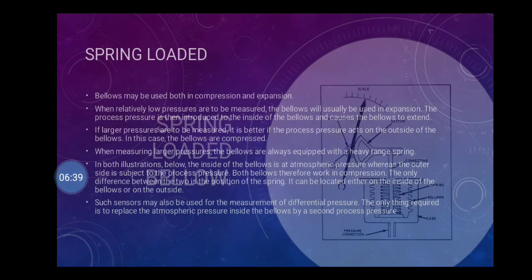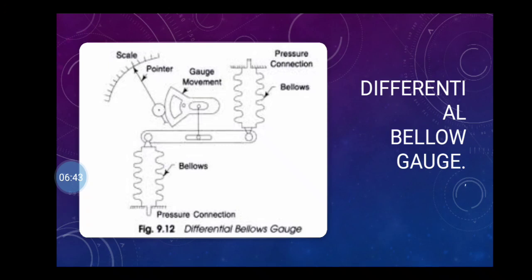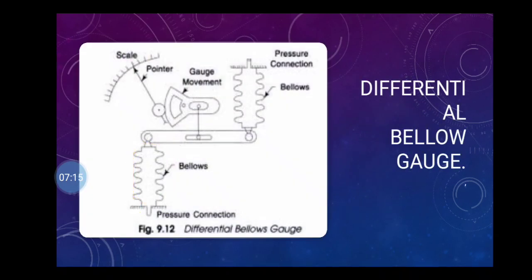Now let's move toward the differential bellow gauge. The differential bellow gauge consists of a scale, indicator, pointer, gauge movement, pressure connection, bellows and linkage. Okay. In this type, one pressure is applied to the inside of one bellow and the other pressure is applied inside the second bellow, because here you can see two bellows, one here and one here. Both bellows are sealed by a link. The deflection mechanism operates and the indicator moves on the scale.